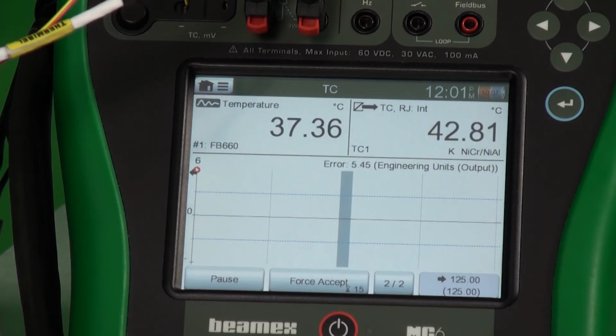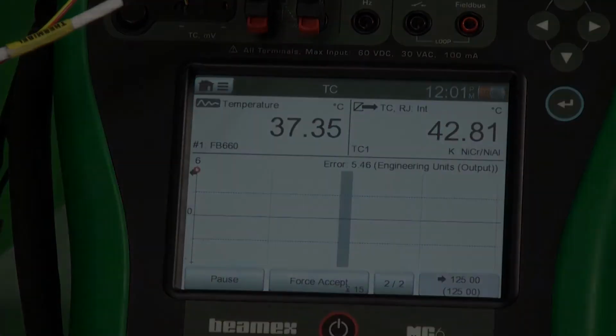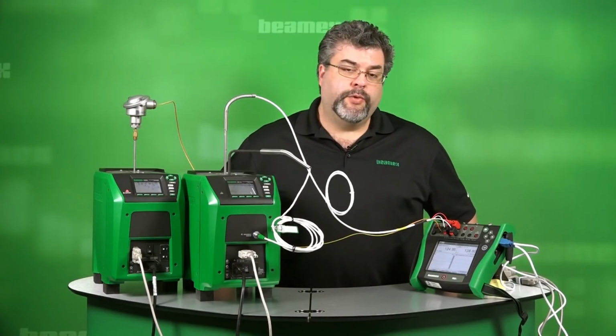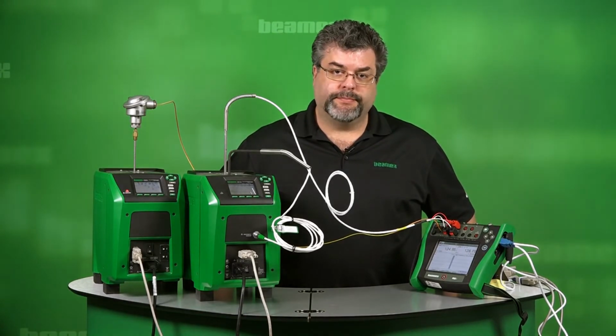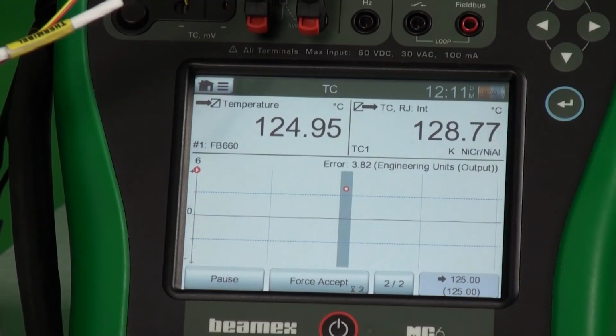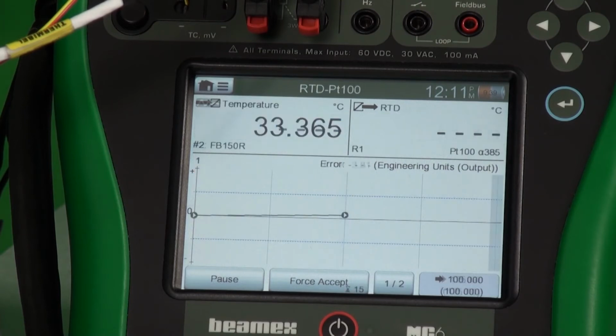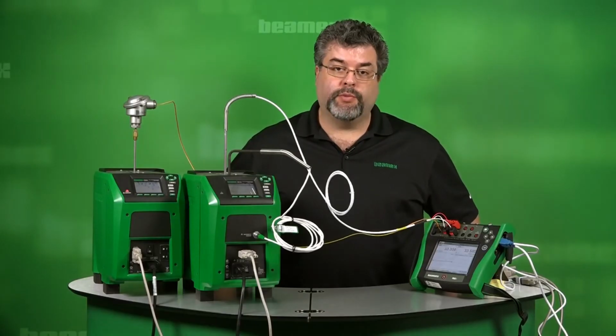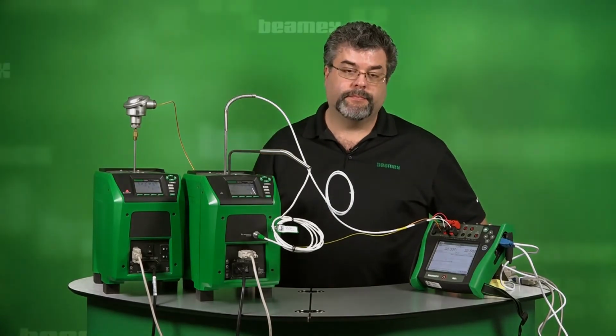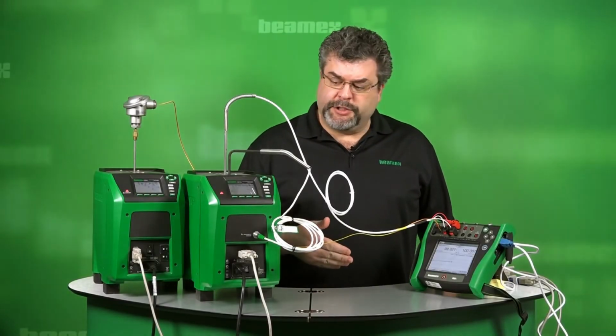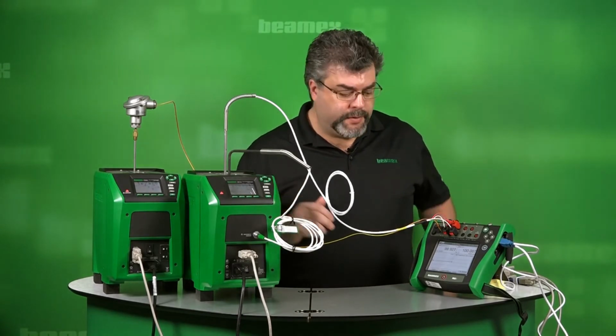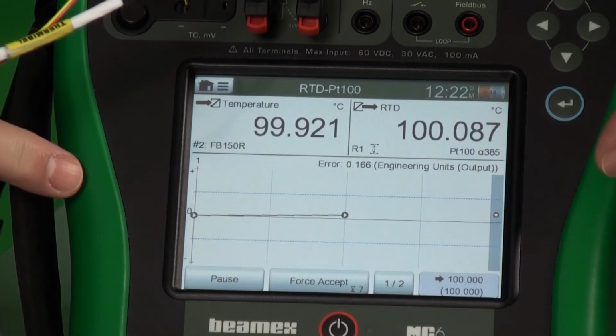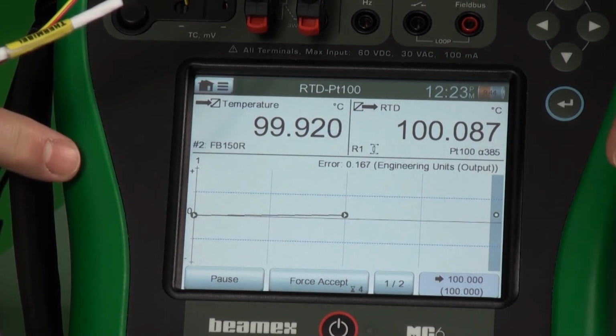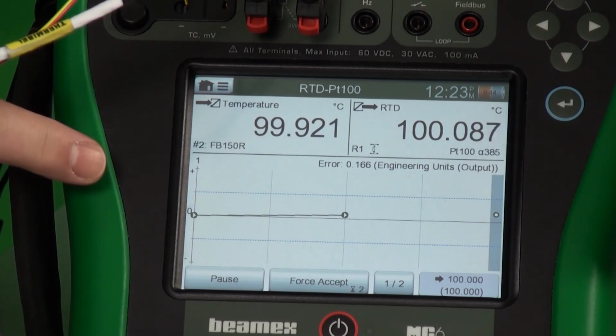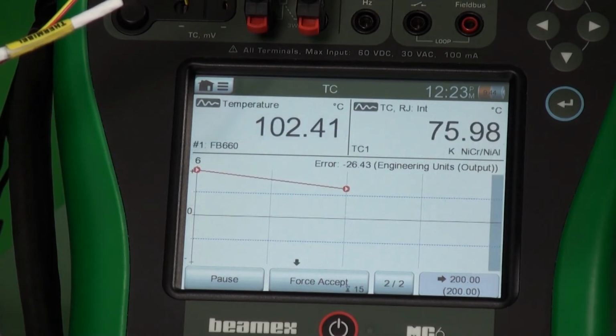The 15 seconds have counted down. Now it will go back to the thermocouple for its second point. We've reached the second point of our thermocouple. Once it grabs that value right here, now it'll move to the third point of our RTD right here. We're at our third and final checkpoint for our RTD. One thing you can notice, the dots are all green and they're within these blue lines above and below this 0.